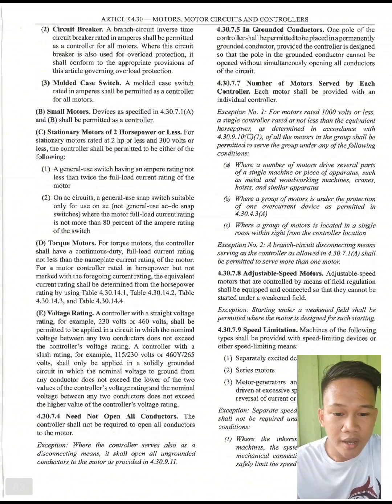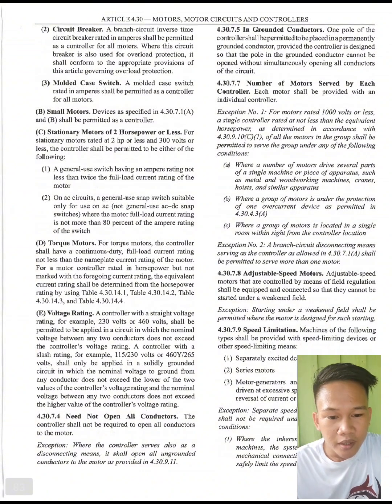Next is voltage rating. A controller with a straight voltage rating, for example, 230 volts or 460 volts, shall be permitted to be applied in a circuit in which the nominal voltage between any two conductors does not exceed the controller voltage rating. A controller with a slash rating, for example, 115/230 volts or 460Y/265 volts, shall only be applied in a solidly grounded circuit in which the nominal voltage to ground from any conductor does not exceed the lower of the two values of the controller's voltage rating, and the nominal voltage between any two conductors does not exceed the higher value of the controller's voltage rating.